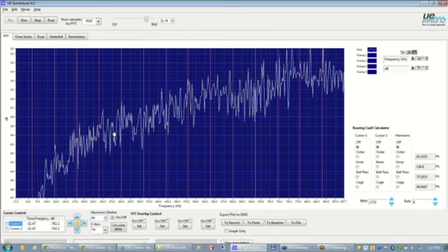The other thing I look at on FFT is the amount of frequency noise that is in between each of the harmonics. So if we look in between each red line, we can see there's an abundance of activity or frequency noise that's occurring in between all 60 Hertz harmonics. Those two things right there are a signature that I am looking for that tells me one and only thing. Either the recording is related to an electrical anomaly or it's related to a mechanical or some other type of anomaly.